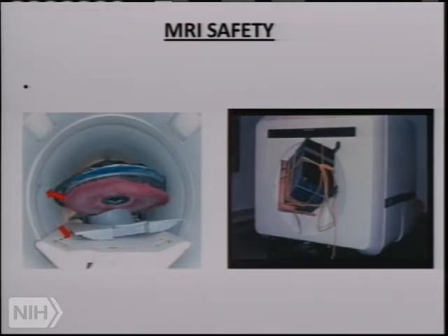So here are some horror stories. That's a floor buffer that people didn't realize. One of the things is people think that when you turn the lights out in the scanner, the magnetic field is off. No, the magnetic field is always on. So even in the middle of the night when they come in to buff the floor, you can have a total disaster. Good news is nobody was in the magnet.